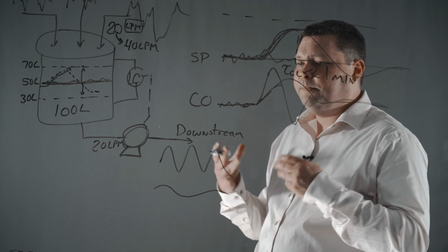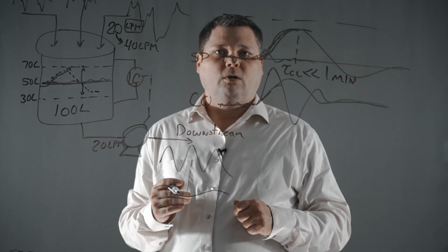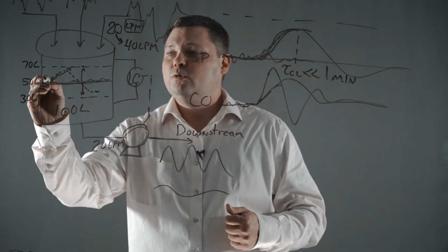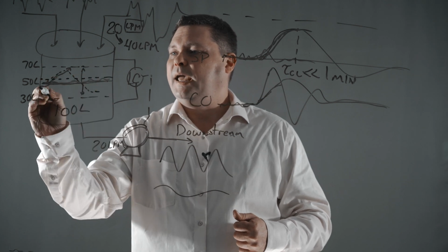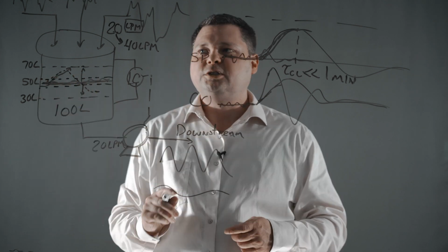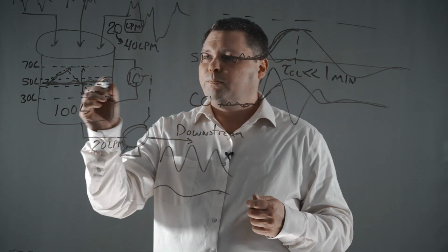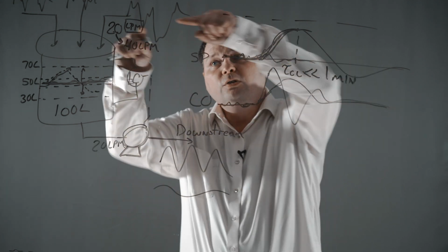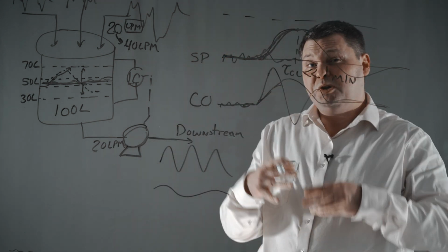Now, you may be saying, hey, Bob, yeah, that's great. That's a surge tank. But I have to do tight level control. The same theory applies. If you tighten your tolerances down here to say, hey, look, I only have plus or minus 1 liter, or 5 liters across my set point, you still do the same calculation, but what you're going to end up with is an arrest time that could be drastically smaller.